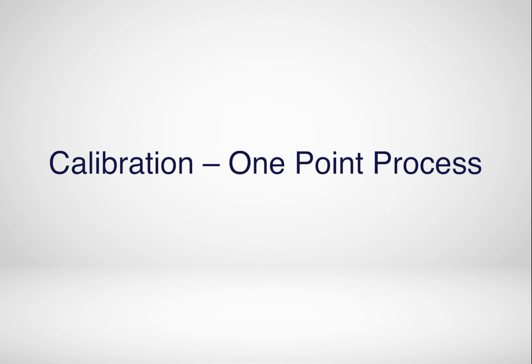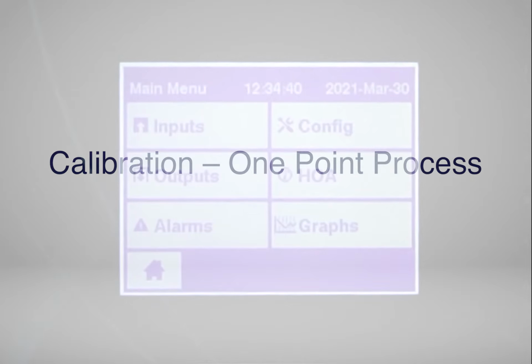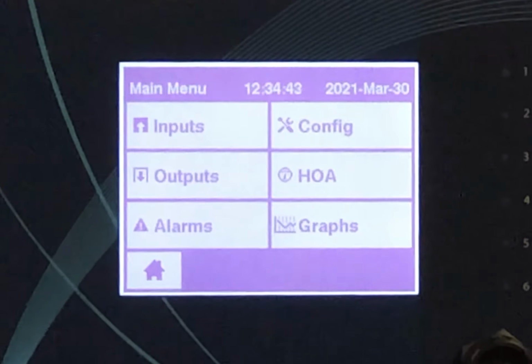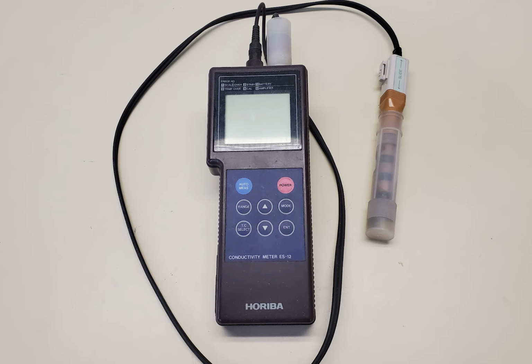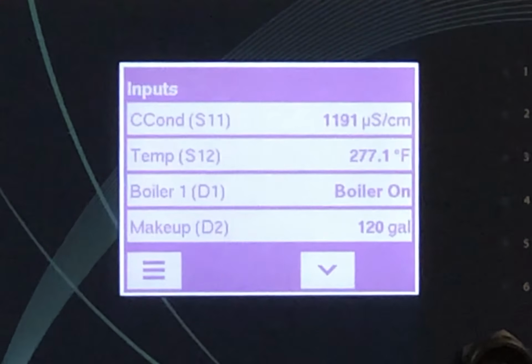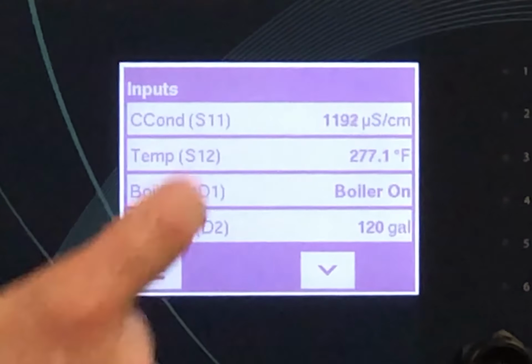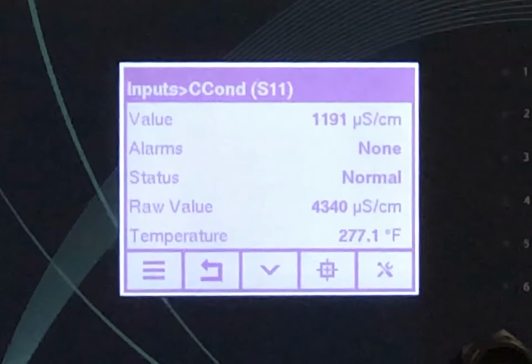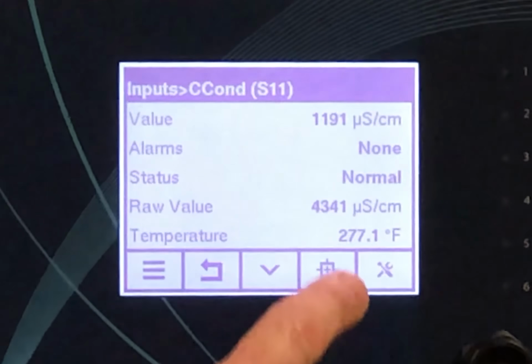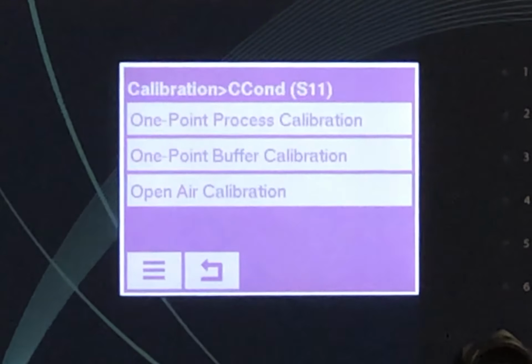To calibrate the boiler conductivity sensor, we'll need to do the following. First, take a boiler sample and measure its conductivity with any handheld device. Then, go to the inputs page. Select the sensor you want to calibrate, in this case, sensor S11. Next, you'll select the calibration button, which looks like a bullseye on the menu. You'll now see the calibration options. You'd want to select one-point process calibration.